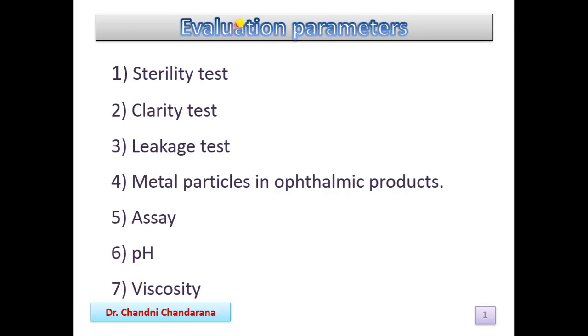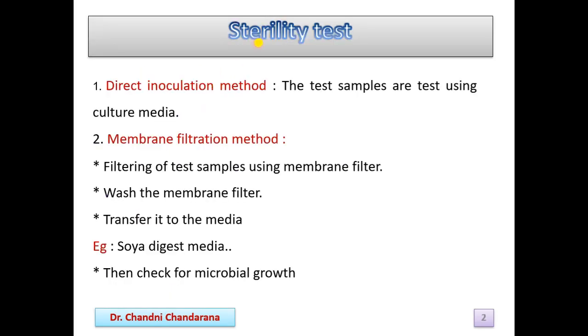These evaluation parameters are there because we have to check that our essential requirements are fulfilled or not. Now, the first test is the sterility test. The sterility test can be performed by two methods: first is the direct inoculation method, and second is the membrane filtration method.